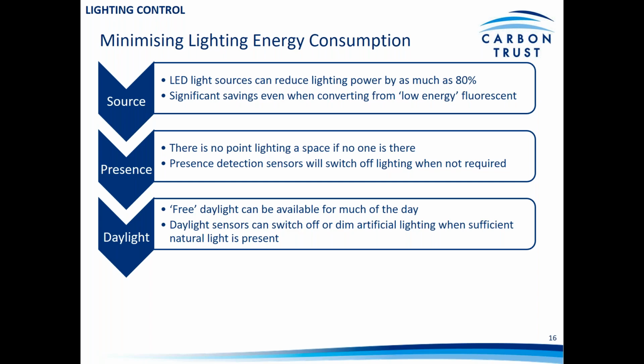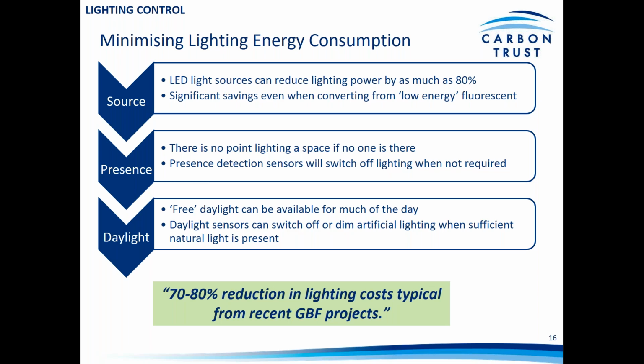So you'll get good savings from changing your lighting, but it's always worth looking at bringing in controls both at that point and even after you've installed LED light sources. It can be beneficial to bring in forms of control such as presence detection, which will sense whether there's anybody in the space and switch off lighting when it's not required, and also the use of daylight dimming. So in many buildings, you'll get good available light through roof lights or through windows through much of the day. And by integrating your lighting system with daylight sensors, they can switch off or dim when sufficient natural light is present. So for lighting projects, whenever you're coupling changes to LED with controls measures, you can see savings of 70–80% plus, and that controls measure will just enhance your savings further whenever it comes to lighting projects.